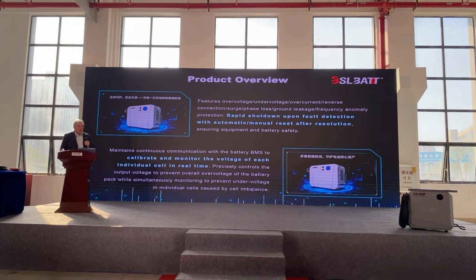The charger has what people call hot disconnect, micro shutdown, or rapid shutdown—when there's fault detection, either from a hot disconnect from someone unplugging the forklift without turning the battery off, or any type of power interruption, the charger has a micro disconnect that can instantly cut power from the battery to limit backflow and prevent damage.